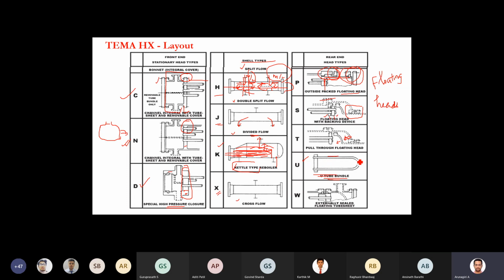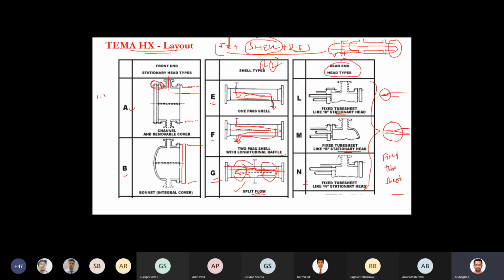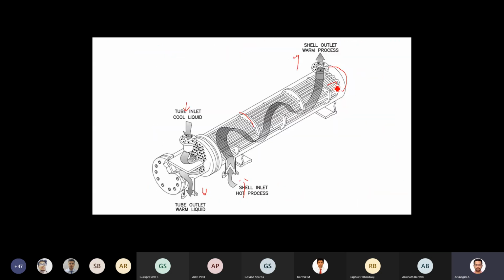Here you have two different passes. Here again this portion plays a major role. Because of bending, what will happen? The thickness of the wall will come down. Thinning is possible, so we have to account for it. Also, the arrangement of tubes in a U-tube is very complicated. Here you can see in this diagram. You can arrange the U-tubes like this. Sometimes it would be like this.